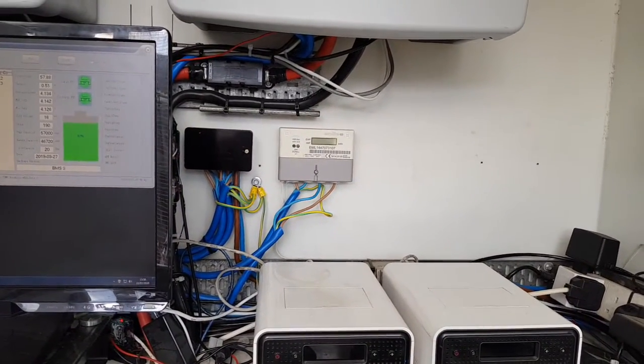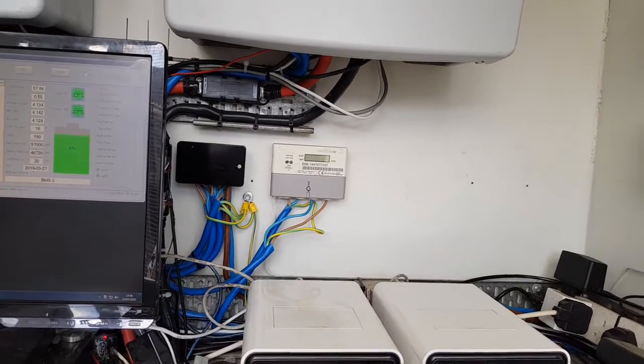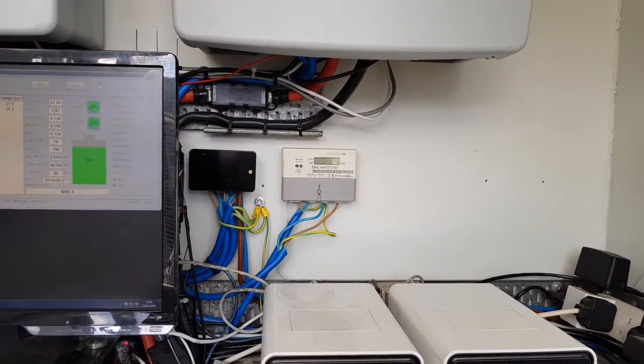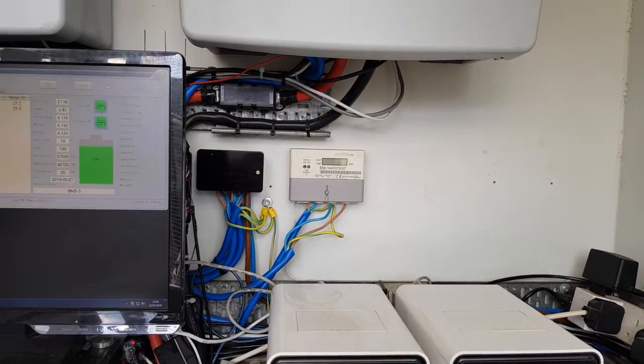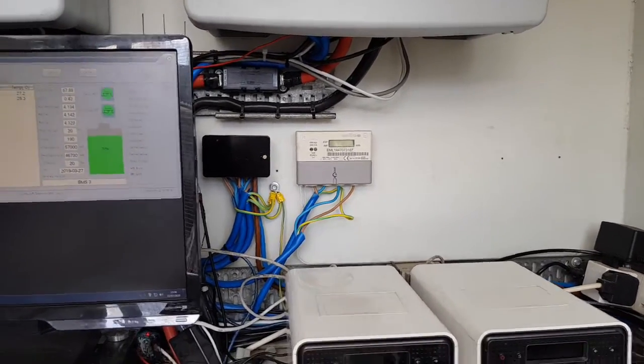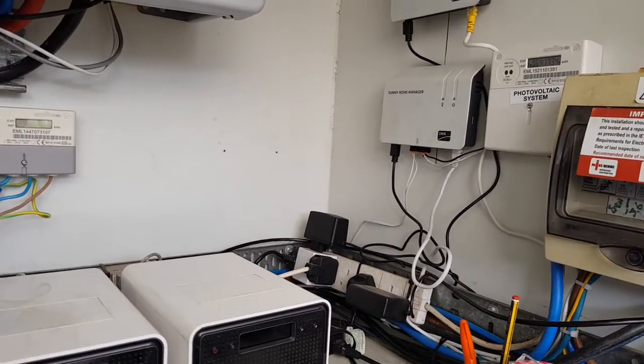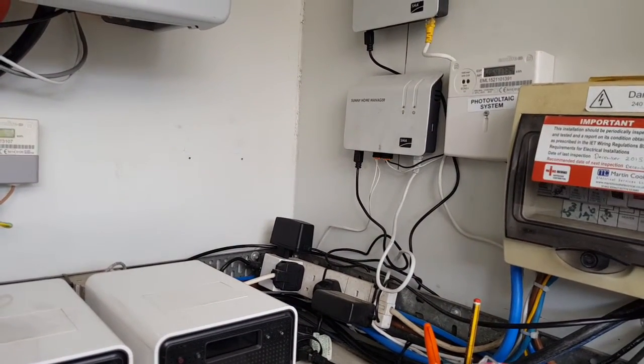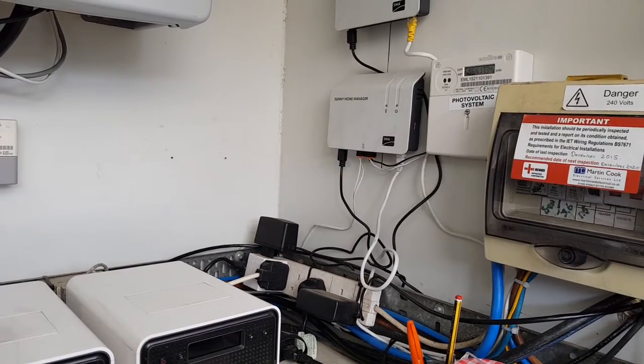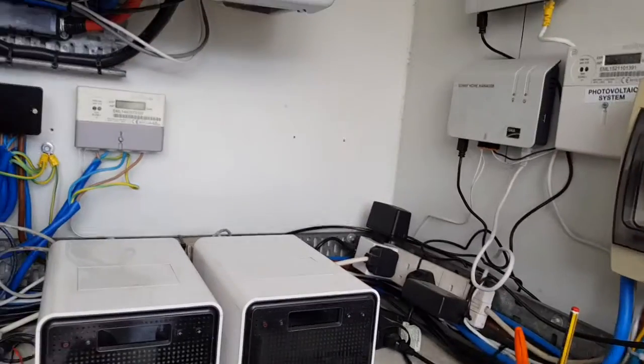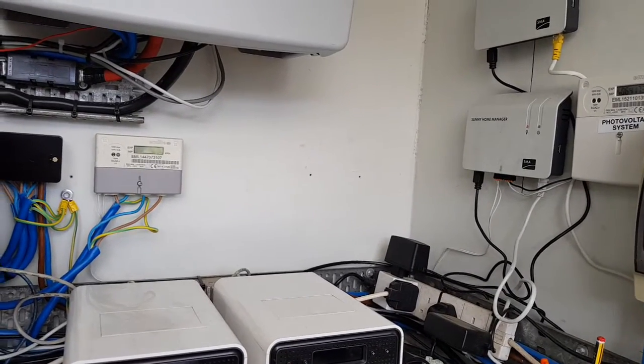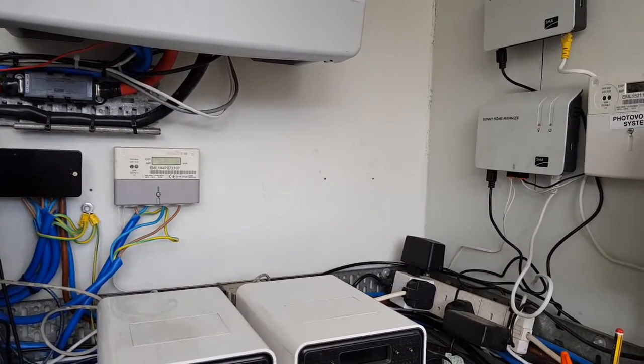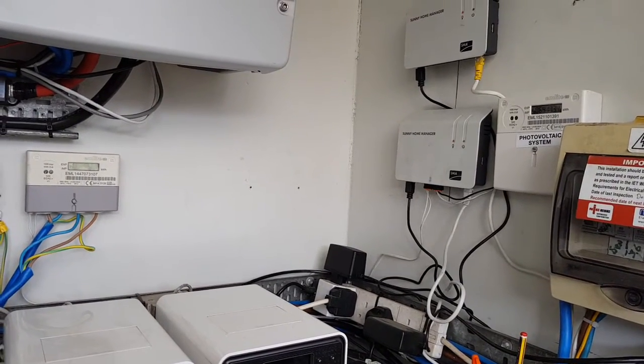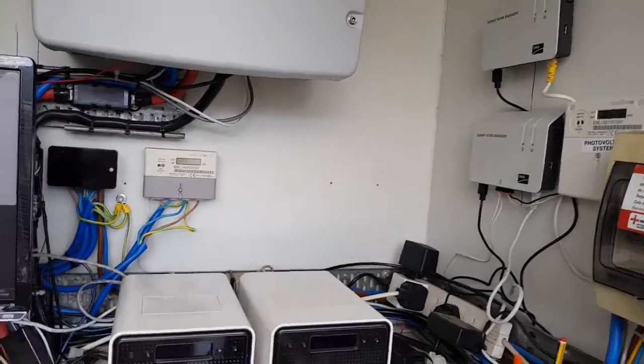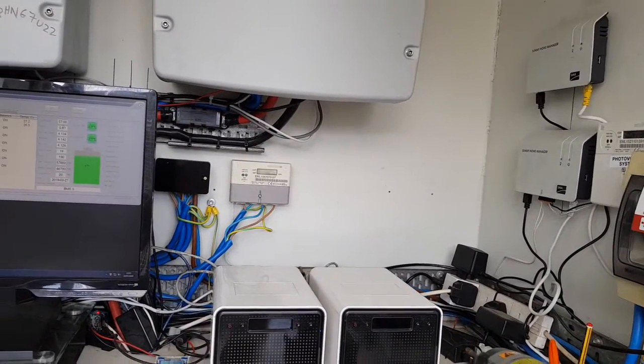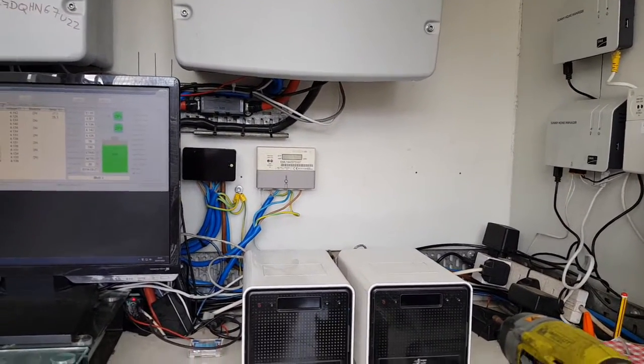What they do is pulse an output. If the blinky lights are blinking, it's using power, and the white wire goes all the way round, the two little skinny white wires, into the bottom of the Sunny Managers, measuring those pulses. In this case, most people would be having that one as the household supply. That's basically what the little clip-on meter over the blinky light does too, but it measures the same thing, it's 1,000 pulses or so per kilowatt.